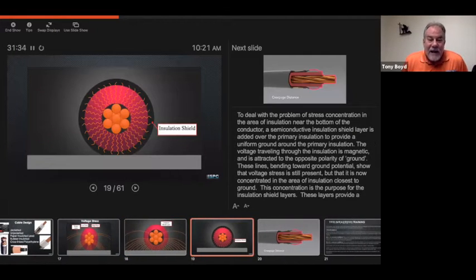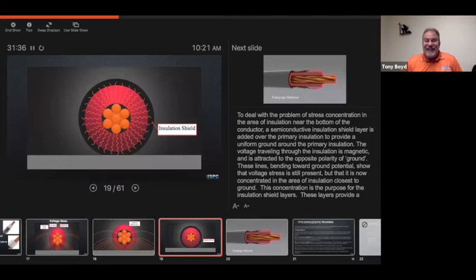All right. And when we add that insulation shield on top of the insulation, that's what causes the stress to go out evenly all the way around through the insulation. It's such a minor leakage current.